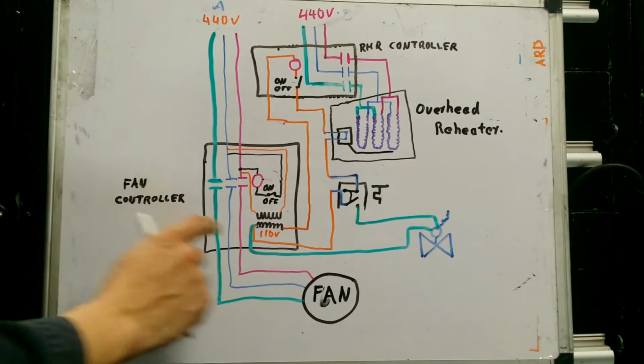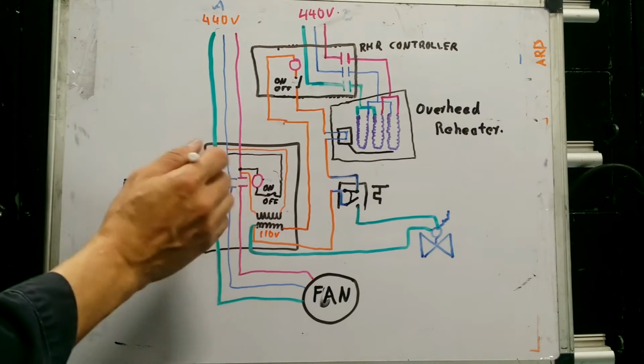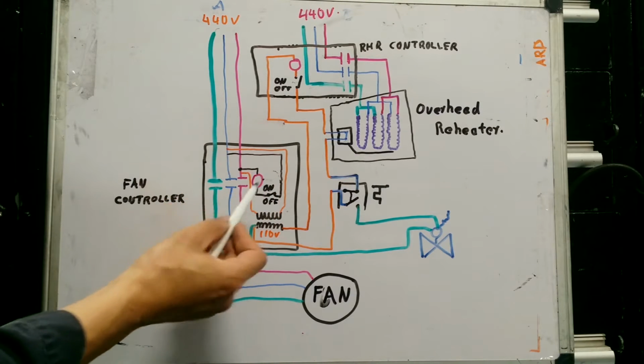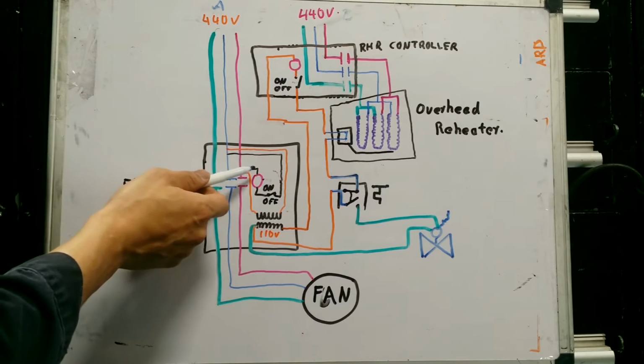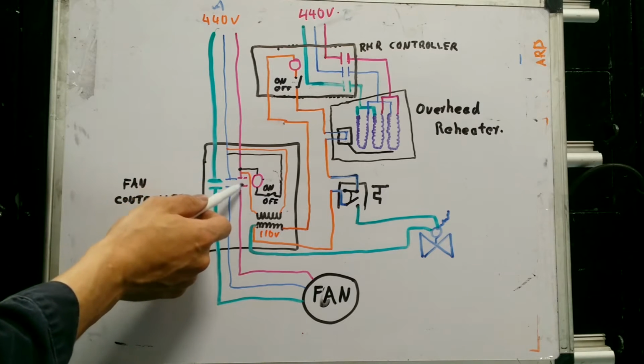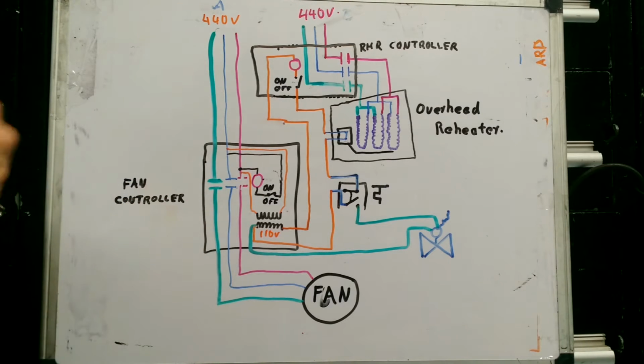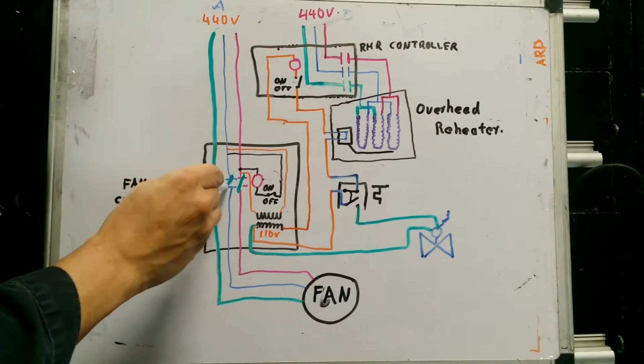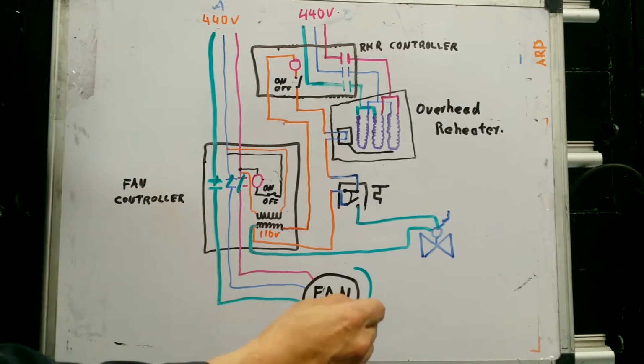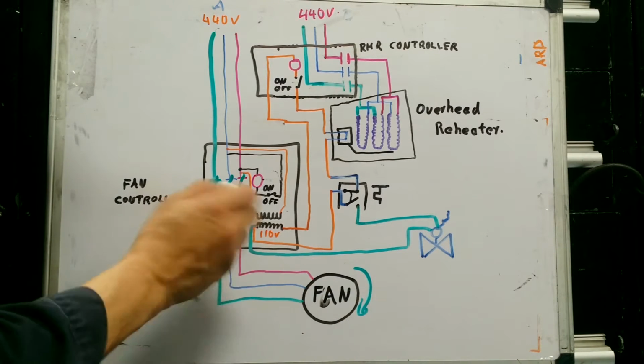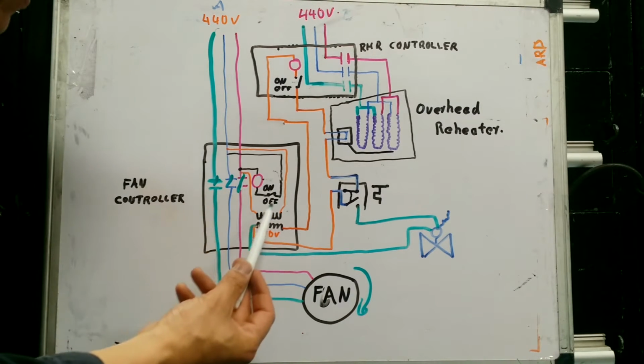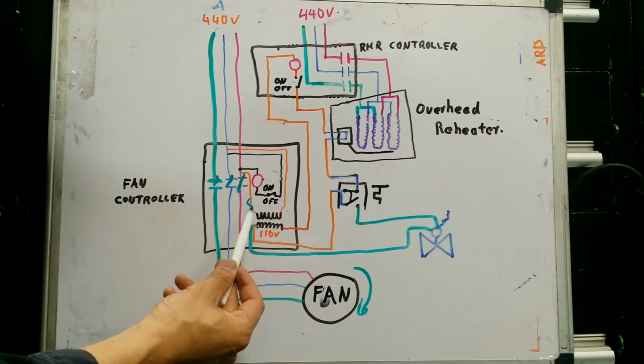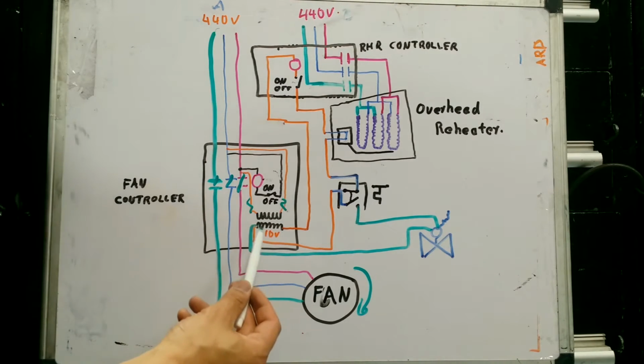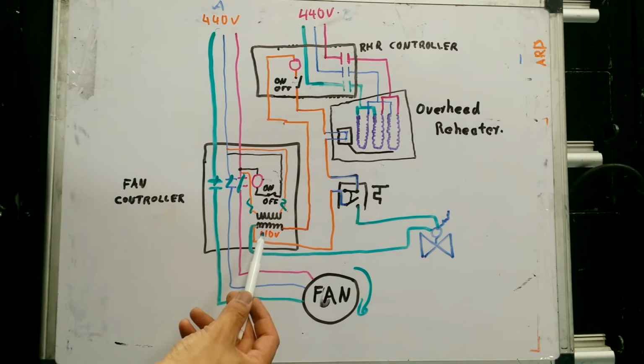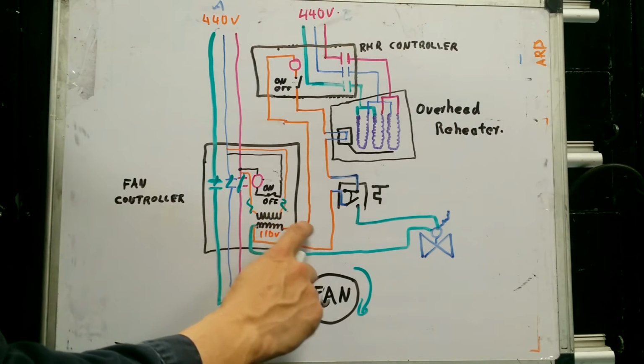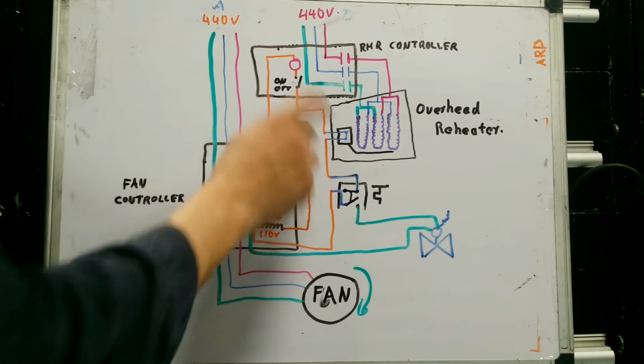Now, whenever somebody presses the on switch for the fan, as you already know, the coil for the contactor energizes and closes these contacts, and power will flow into the fan and the fan will spin. At the same time, over here, there are these power lines, which are protected by fuses, and they energize this 110 volt circuit. The 110 volt circuit is now the orange line, at least for the reheater side.